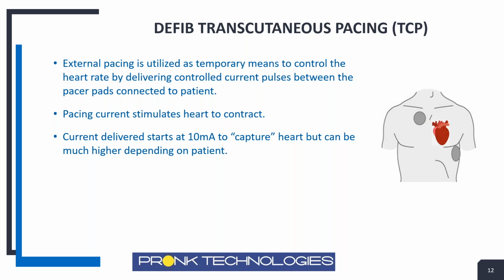And that current necessary to capture the heart can vary depending on the person again. As a general rule, about 10 milliamps of current will usually be enough to capture the patient. But on some patients, you may need more current. That's where you see the need to test the defibrillator across different current and pulses per minute, because you want to verify it's outputting the right current, so that if the nurse, the doctor, or the EMT needs to deliver more current, they're doing the least amount of current possible across the heart.